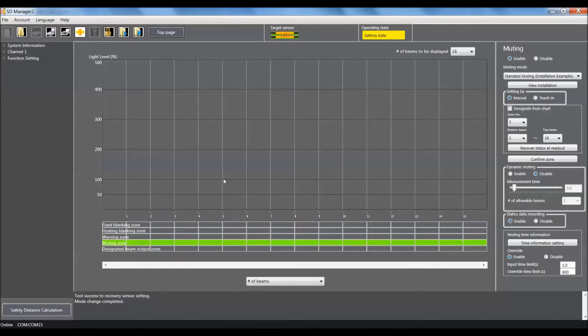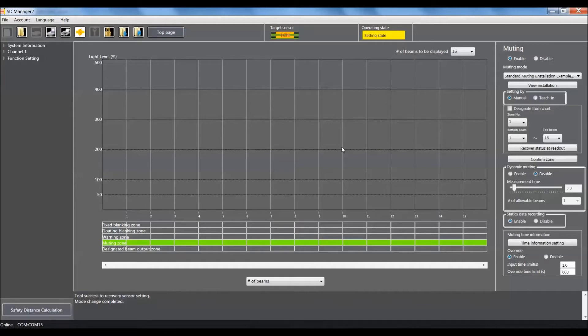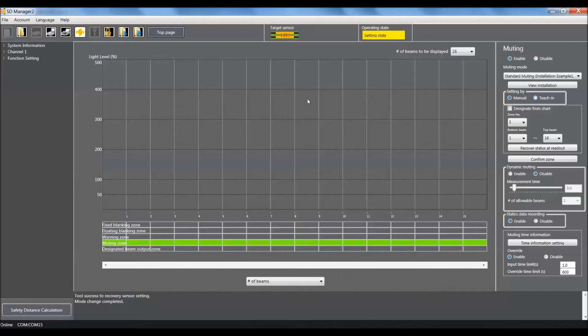We also show where our muting zone is. Presently, it's set up for all 16 beams, so we will shorten that shortly. In this area of the graph, we're able to see what's physically going on while using the automatic teach-in function. We'll be able to visually see how many beams are being blocked by our object.